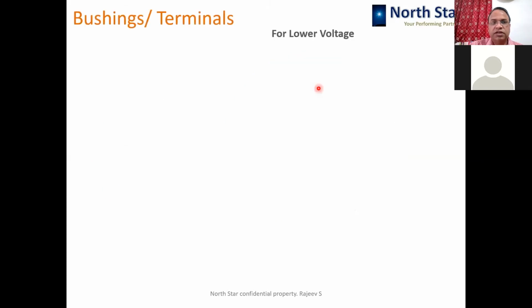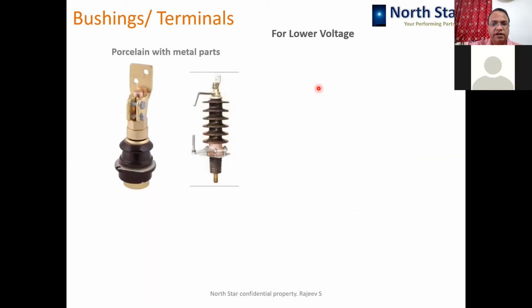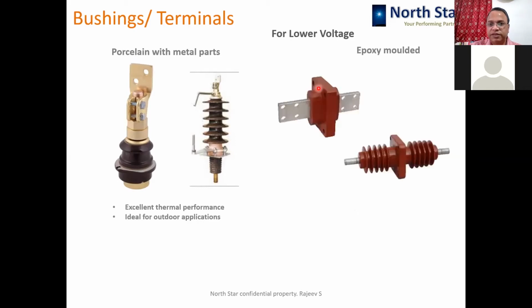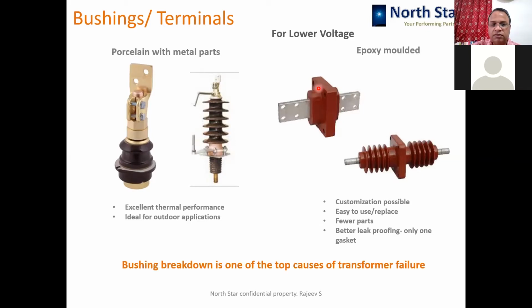So let us look at bushings. What are they, and what kind of issues do they have? On the lower voltage side, we have porcelain type bushings with draw-lead type metal part. They have excellent thermal performance, ideal for outdoor applications. Then we have epoxy molded bushings, which are now quite popular as they are very easy to use. Very easily they can be customized, very easy to put, with very few parts, only one gasket, so chances of leakage are very little.